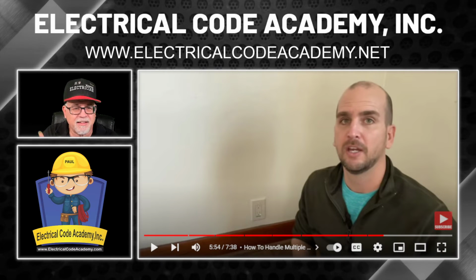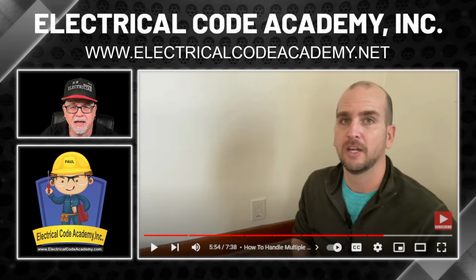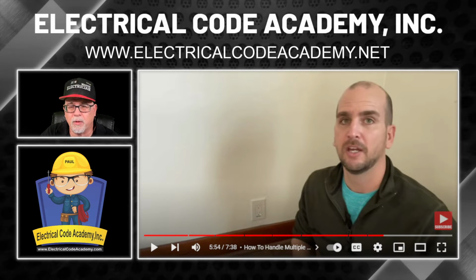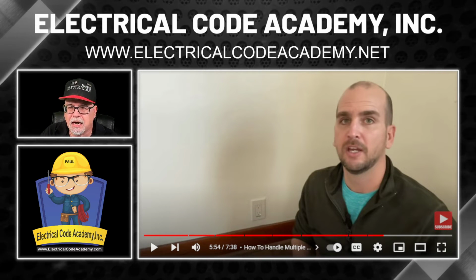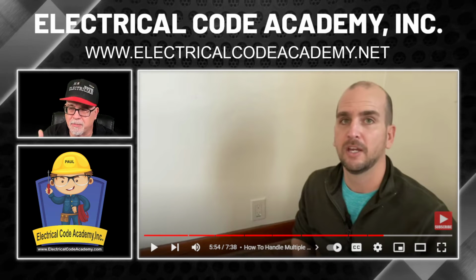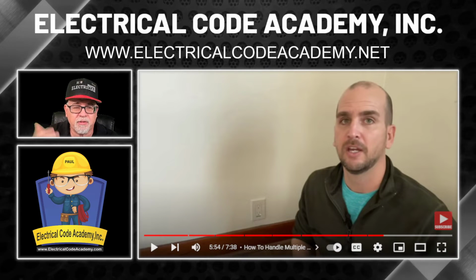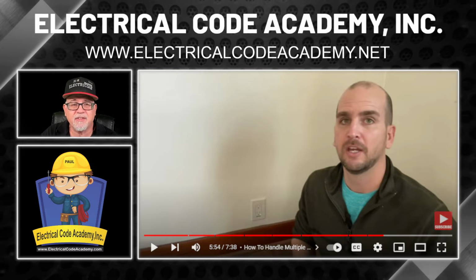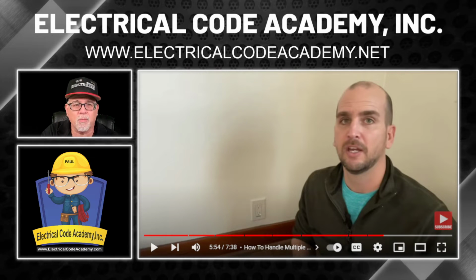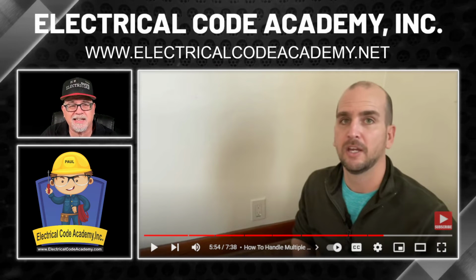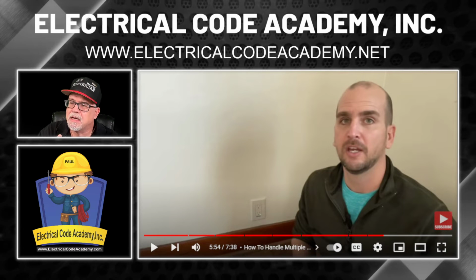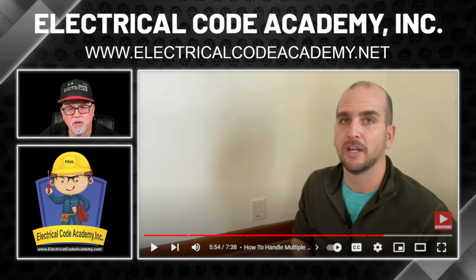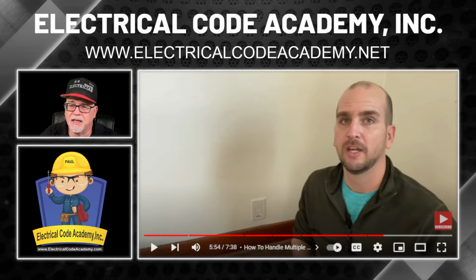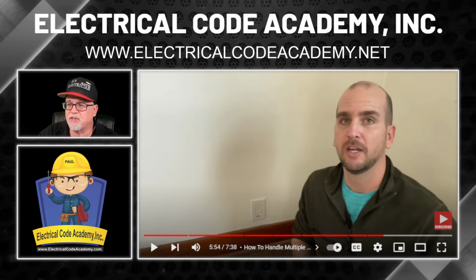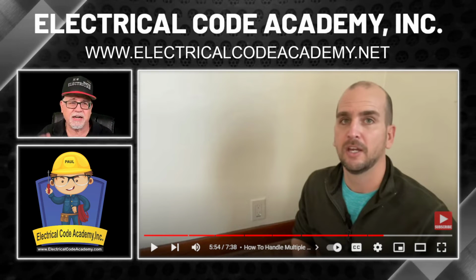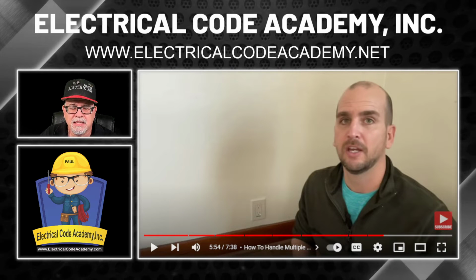We have the GFCIs like this are Class A, and that is the 4 to 6 milliamp, we call 5 milliamp threshold. And then, of course, we have Class B, which is typically 20 milliamps or 30 milliamps, depending on the manufacturer. That is not going to protect people. That's more for protecting property and equipment that's connected to it, things like that. And then it starts getting into things we call special purpose GFCIs, and again, for three phase applications and whatnot. So again, a bunch of different classes of GFCIs that we have.